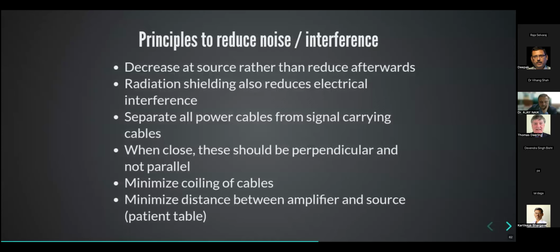Some of the methods to reduce noise: always try to decrease noise at source. So if your signal is noisy, try to identify what the source is. If you have, say, defibrillation patches put on the patient, it might be coming from the defibrillator. Unplug the defibrillator from the wall and see if that reduces it. If it does, the socket into which you're plugged is leaking, and you might have to change to another socket. This can even come from your pulse oximeter probe. Check if earthing any of the equipment reduces the noise. Try to find out the equipment from which noise is leaking in.